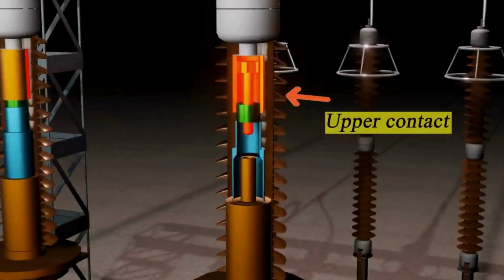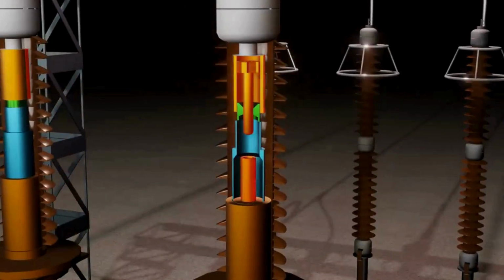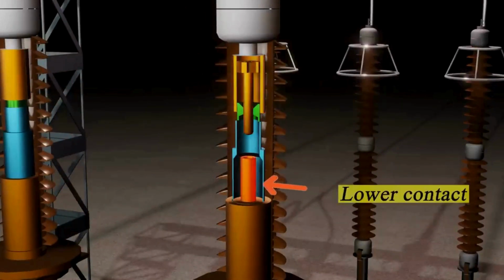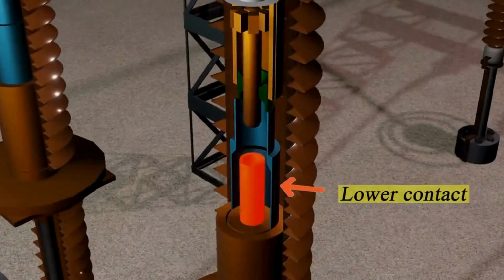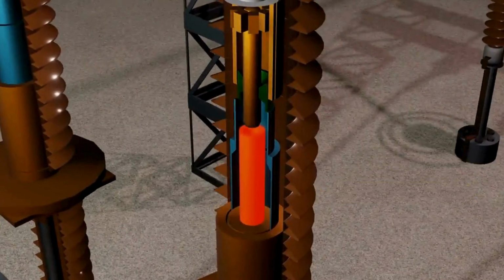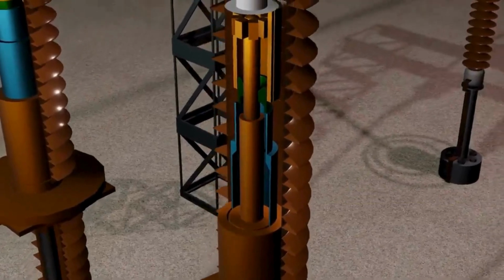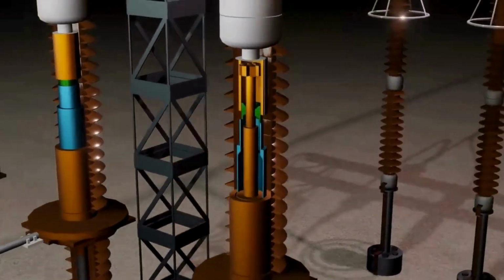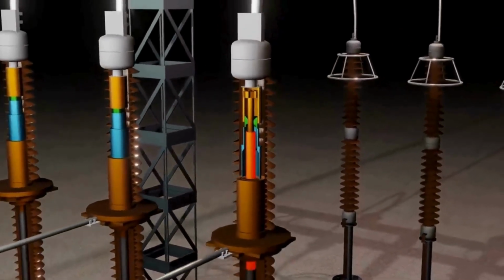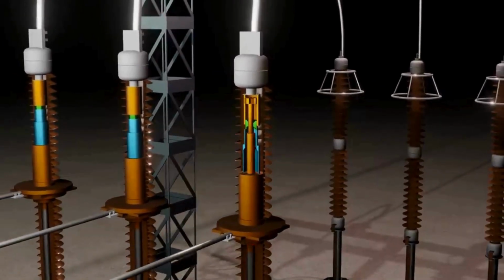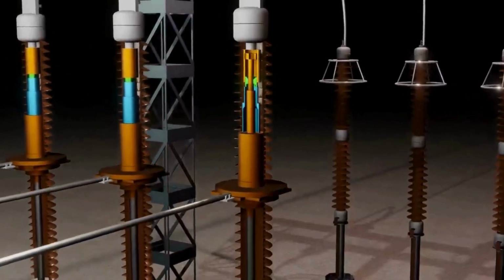The upper terminal is absolutely fixed and cannot be moved at any time. The rod that is stuck here is copper. There is also a copper rod in the lower terminal that can move. This rod is hollow from the inside and makes contact with the upper terminal. Lower contact cannot move itself, but there is a mechanism to move this copper rod. The moving contacts here operate from outside.